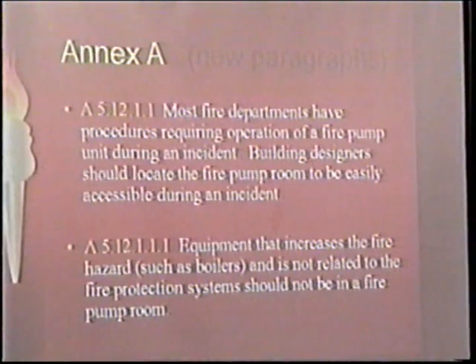If you notice on previous slides, the verbiage in the codes is "shall not" or "shall be." These are "should," okay? Yeah, because legally, "shall" is a directive or a mandate, and "should" is a suggestion or recommendation. I understand, but I've been preaching some of these things for years because it doesn't make a lot of sense to put a natural gas supply in a room that has sparks. But you should check with the AHJ, number one, as far as what their interpretation is, if to them it's "should" or "shall."